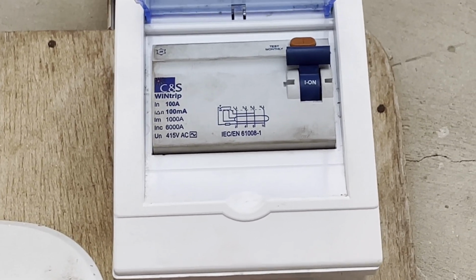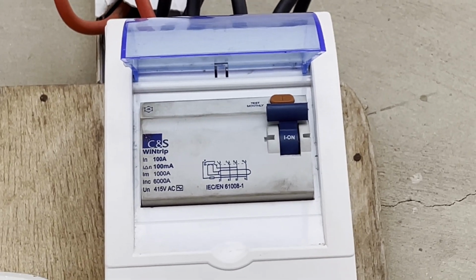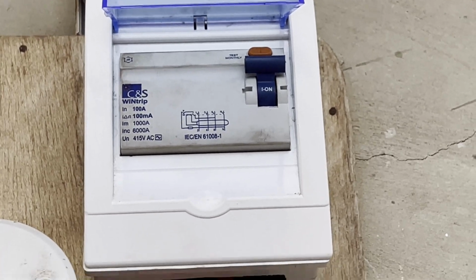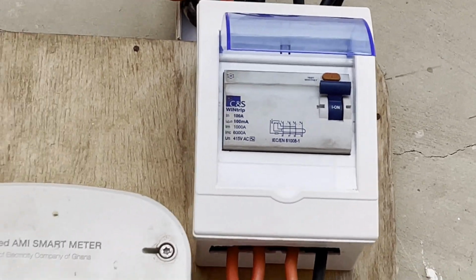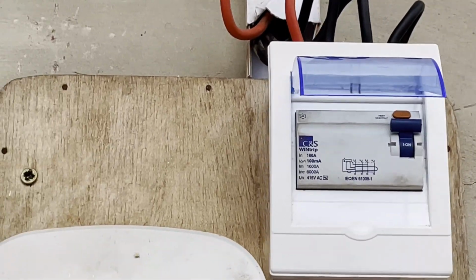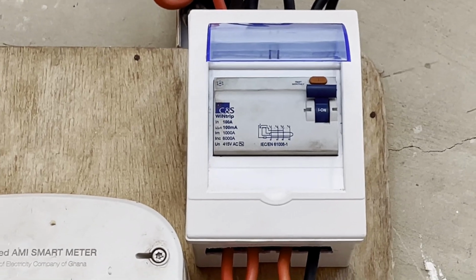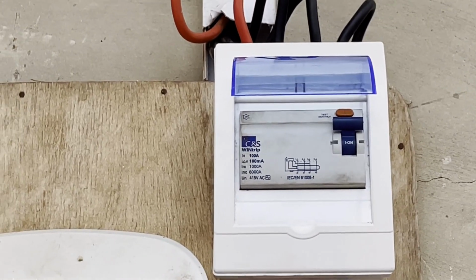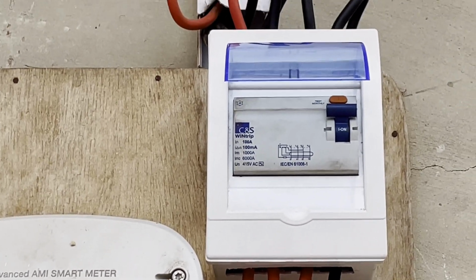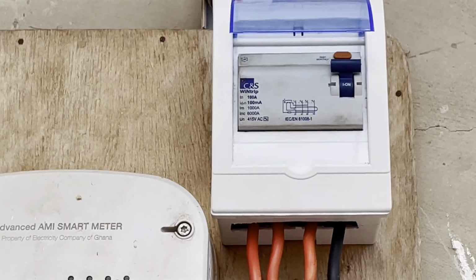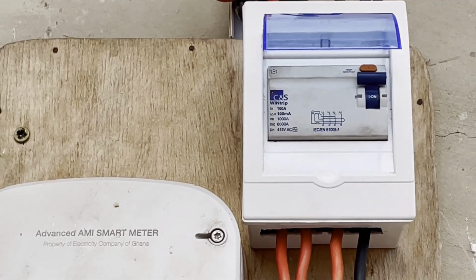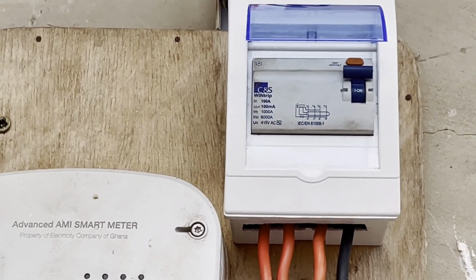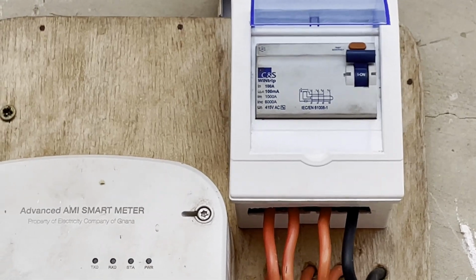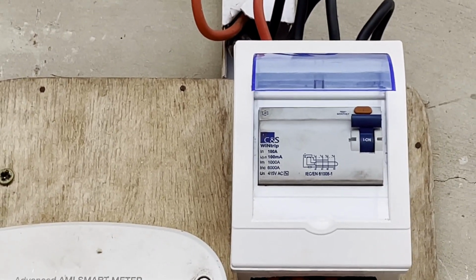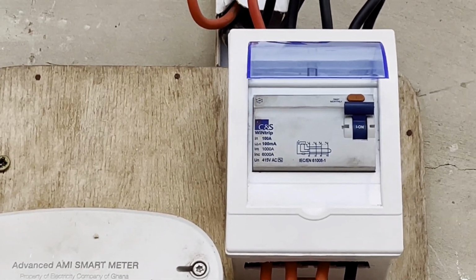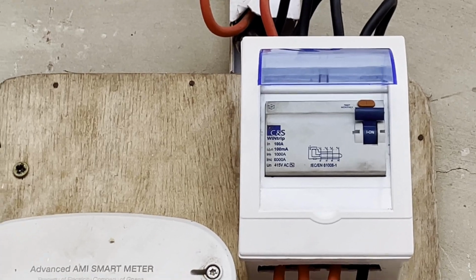Now, there are some clients' homes I've gone to that don't have this, which is very dangerous. Think about the scenario I talked about with the first building finishing point, the window sealing. If the pool of water in my electrical room when we first moved in had made contact with a live electrical part, this device would have saved my life or saved me from a serious electrocution, because as soon as the water touched any live electrical component, if anything live was on the floor touching the water, this device would trip and I'd be fine. This is how important this device is. Very, very important, guys. Do not do your electrical installation without this incoming RCCB.